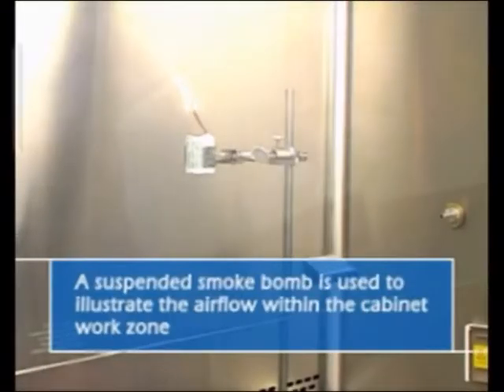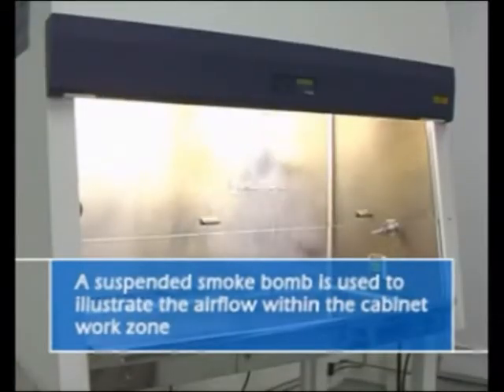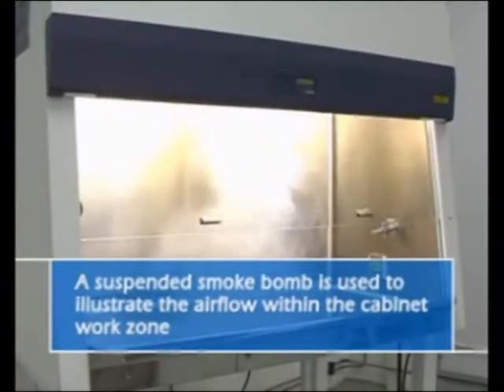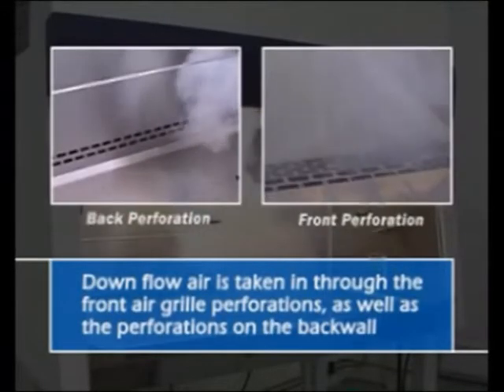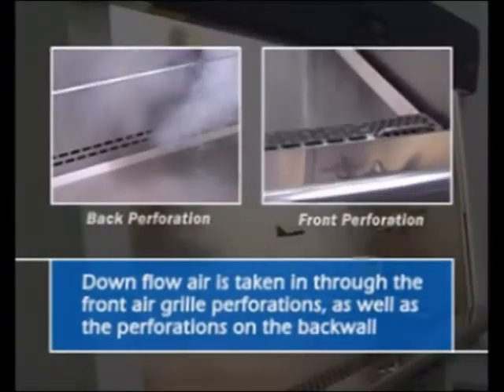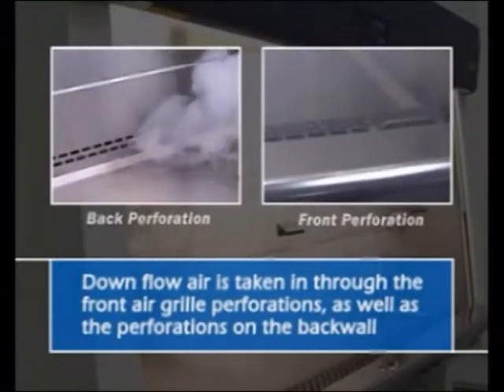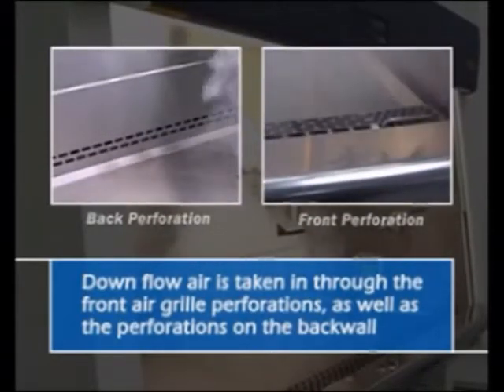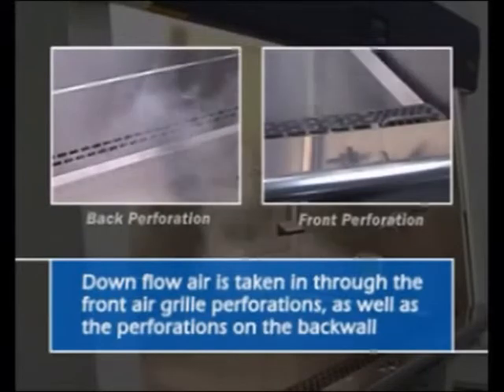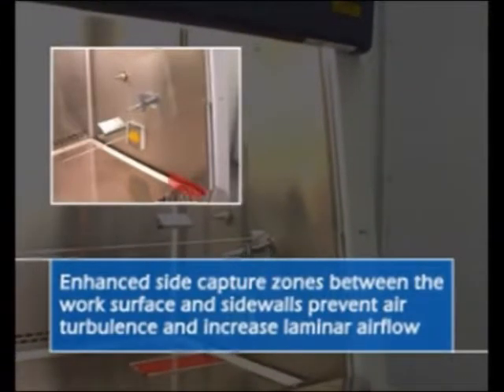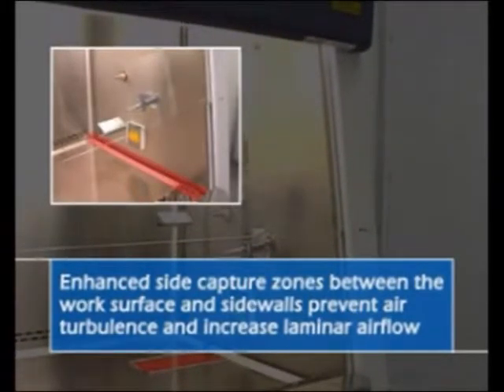The following experiment with a smoke generator illustrates the airflow pattern in a Class II Type A2 cabinet. Downflow airstream splits and is taken in through the back wall perforations and the front air grill. This feature ensures that the airflow streams remain unidirectional and free of turbulence. The enhanced side capture zones between the sidewalls and the work surface eliminate the possibility of the downflow air bouncing off the work tray and creating turbulence.